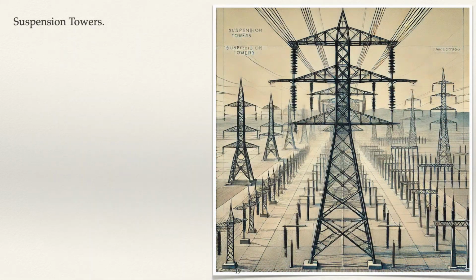Common types of transmission line towers. Suspension towers are used in straight line sections where there are no significant changes in direction or mechanical loading. Its lighter and simpler design compared to angle towers. Supports conductors under normal tension without applying extra forces. Typically used in sections with longer spans. Suspension towers are used in straight sections to handle minimal mechanical load. Heavier suspension towers are used in high wind or icy areas to withstand wind and ice loading.